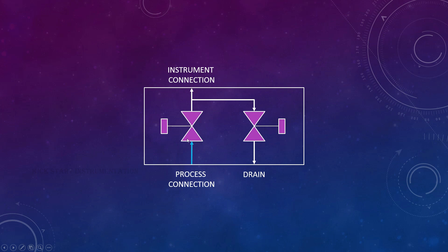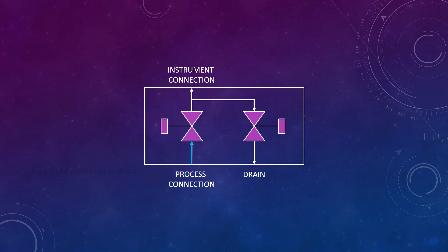Now valve 1 as well as valve 2 are in the closed position. At this position it is safe to install the instrument and connect it with the manifold valve. It will be connected with a male or female connector as per the specification. To avoid leaks, we have to use a small Teflon tape so that it is fixed properly and there is no further leak.